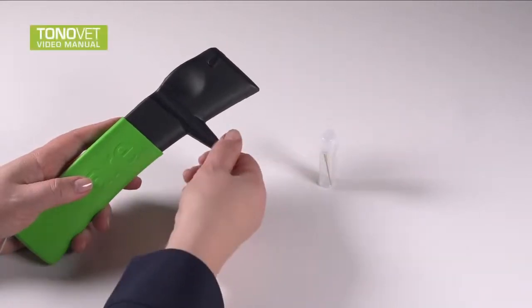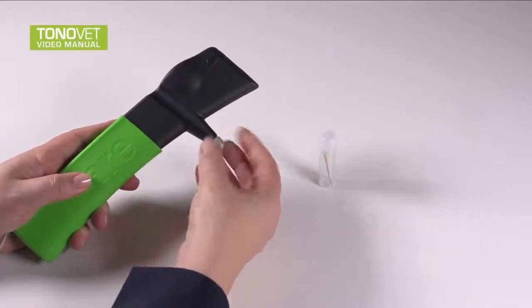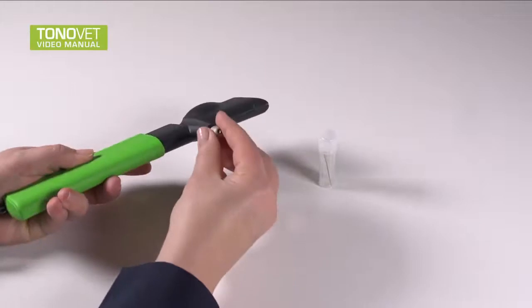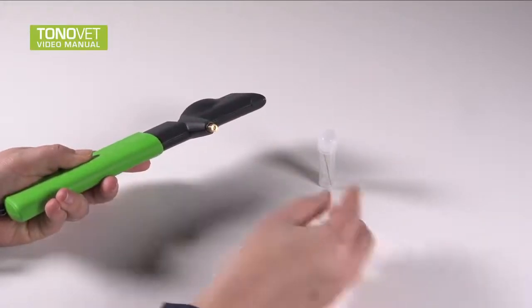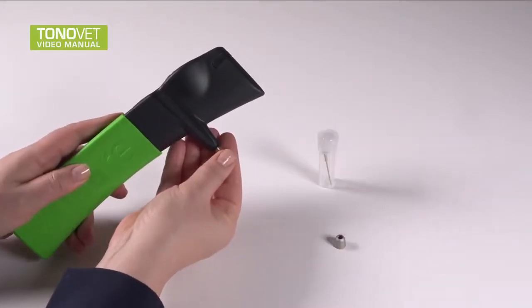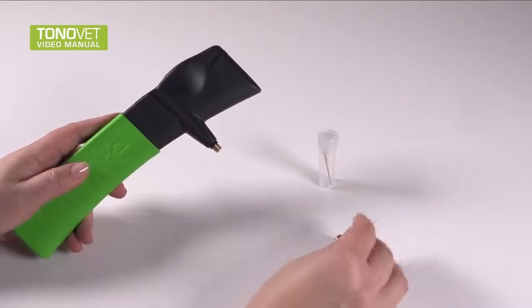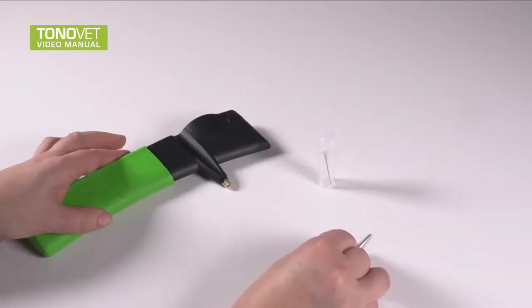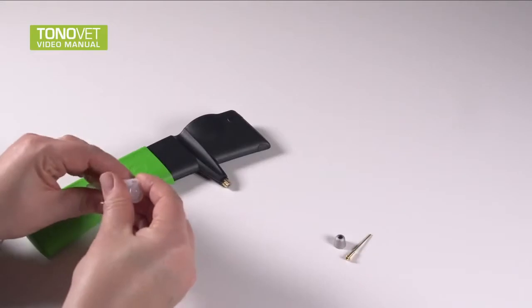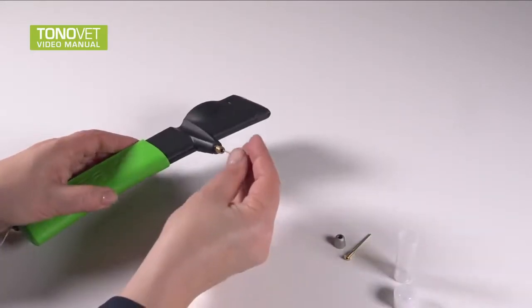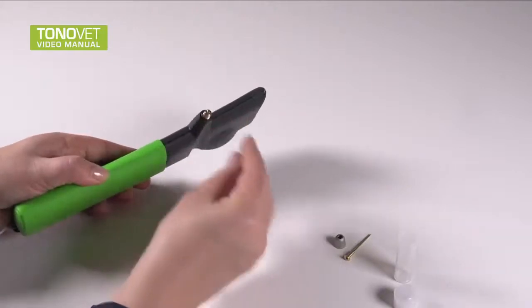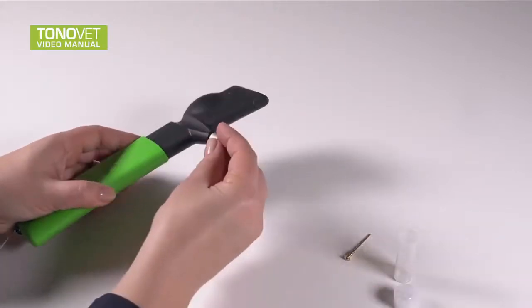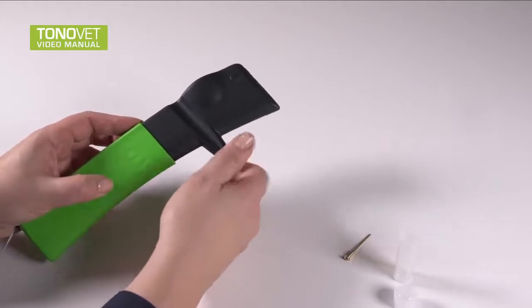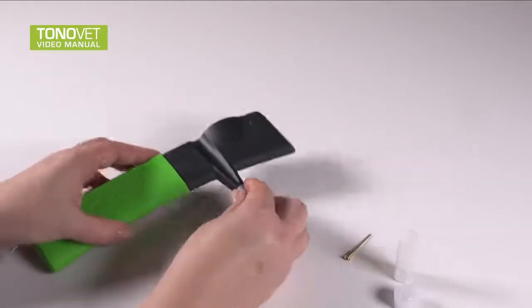To replace the probe base, unscrew the probe base collar. Remove probe base by tilting the tonometer downward and pull the probe base out of the tonometer. Put a new probe base into the tonometer. Screw the collar on to lock the probe base.